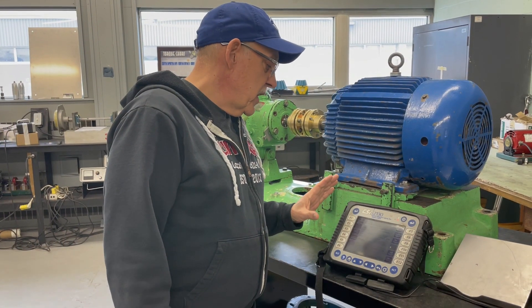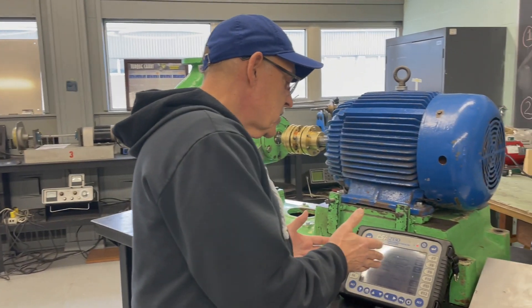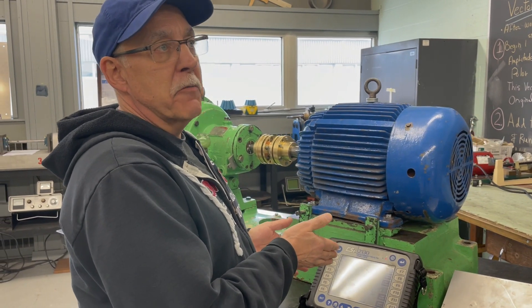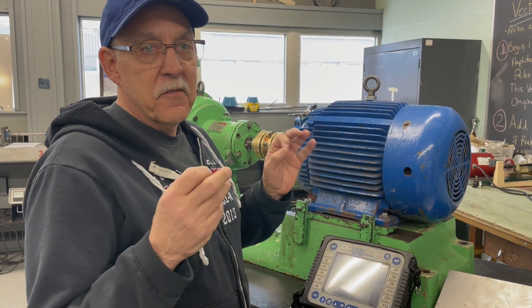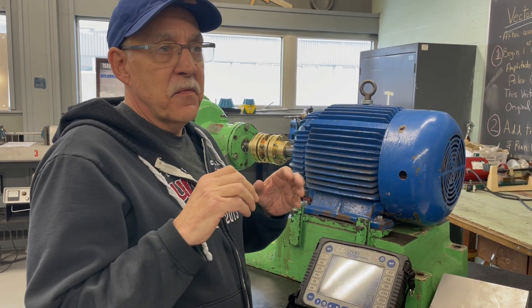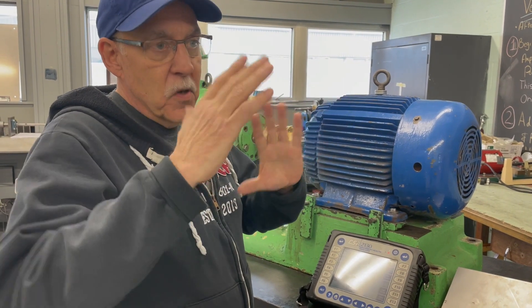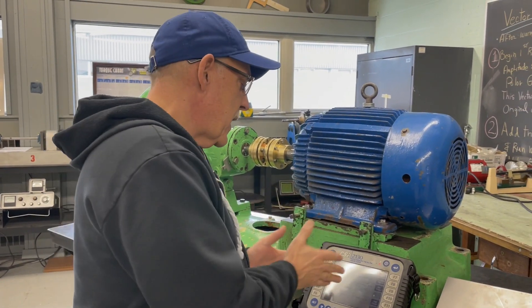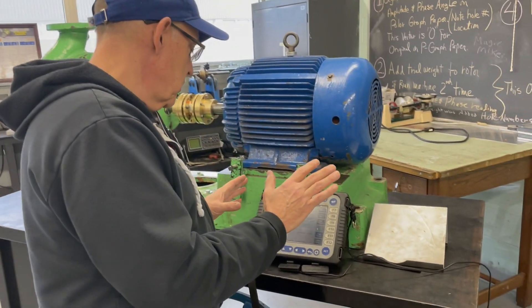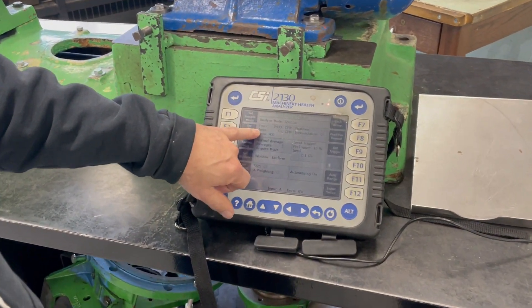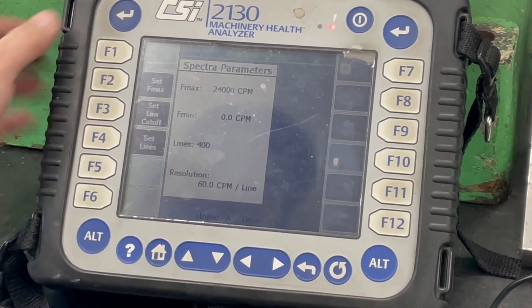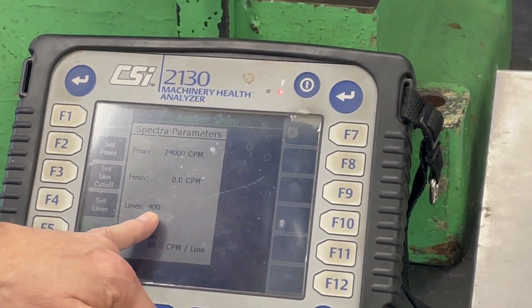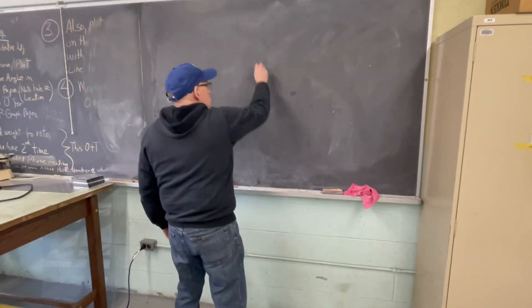The first thing we have to do before taking a reading is set the box up. It's like an old 35-millimeter camera — you had to set the f-max (shutter speed), picture size, and other things. This box is the same way. On the box you can see it says F-max, F-min, and lines of resolution. If I press the button, you can see the analyze mode showing F-max, F-min, and lines of resolution. Let's go to the board to look at our spectrum.